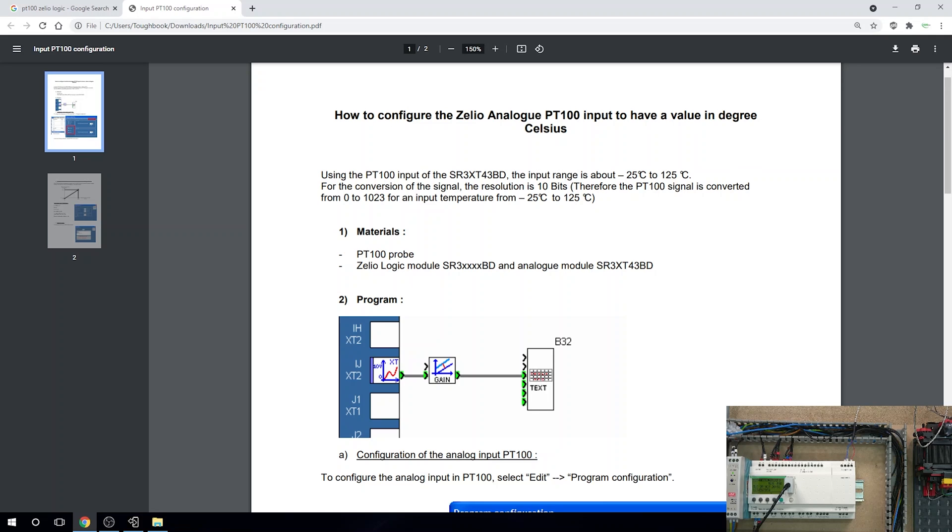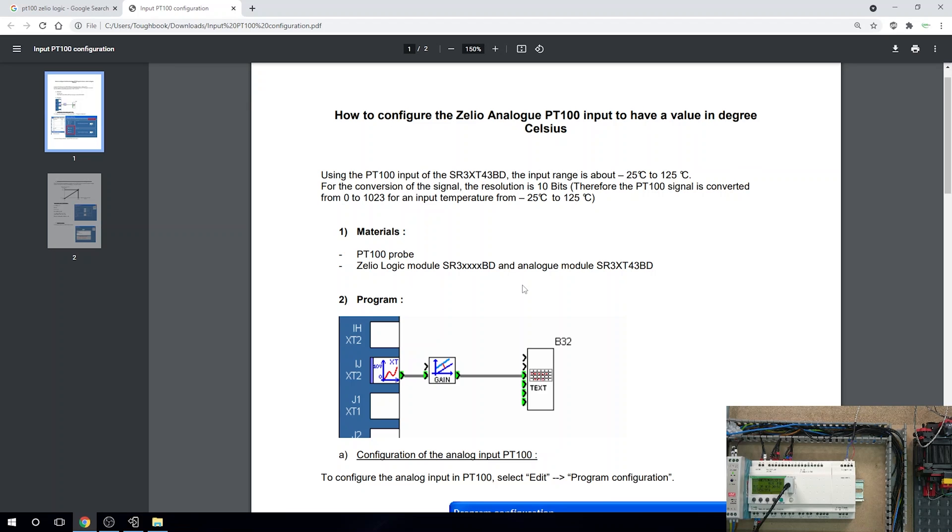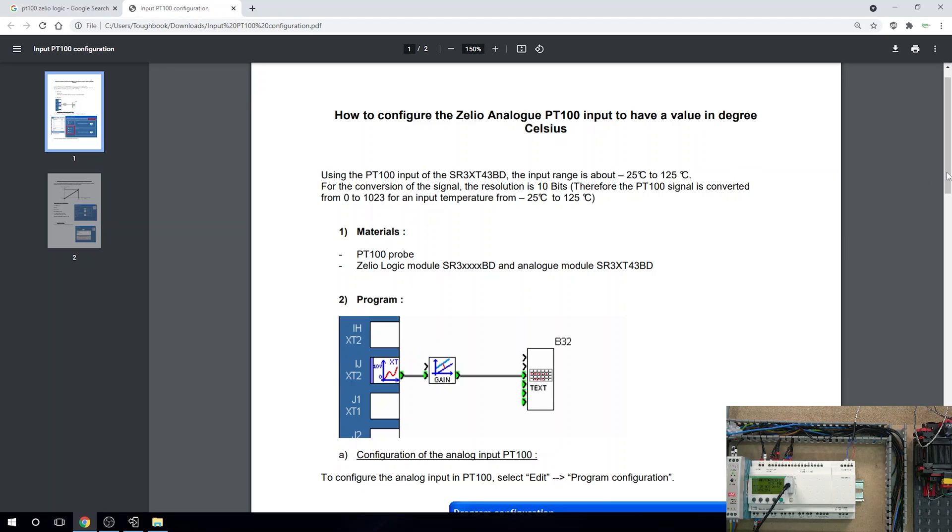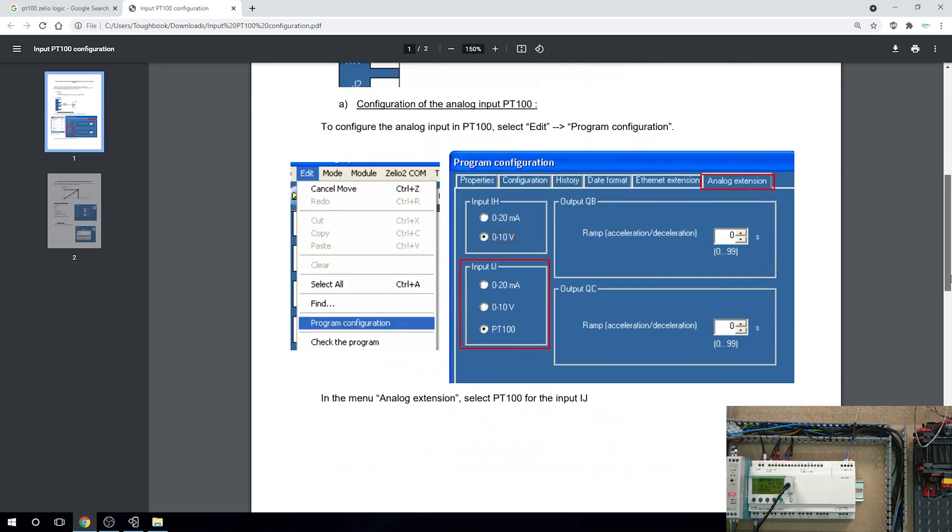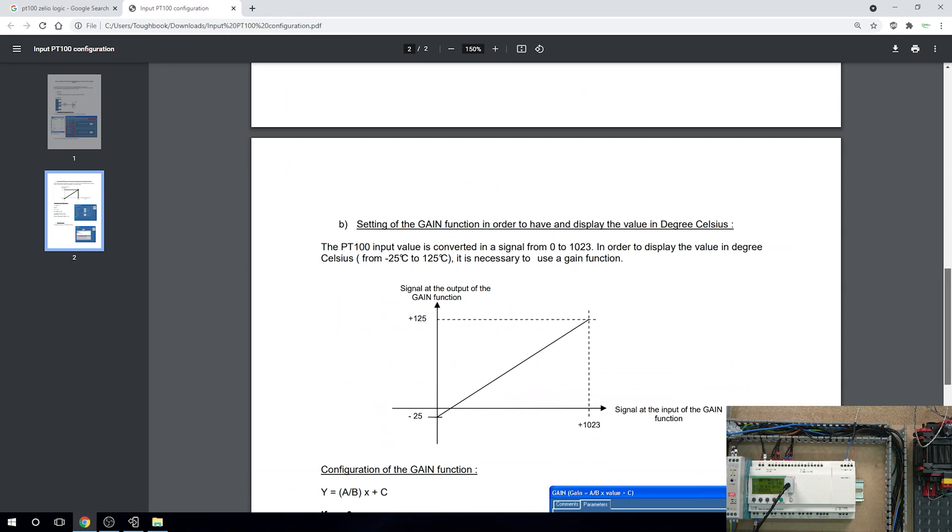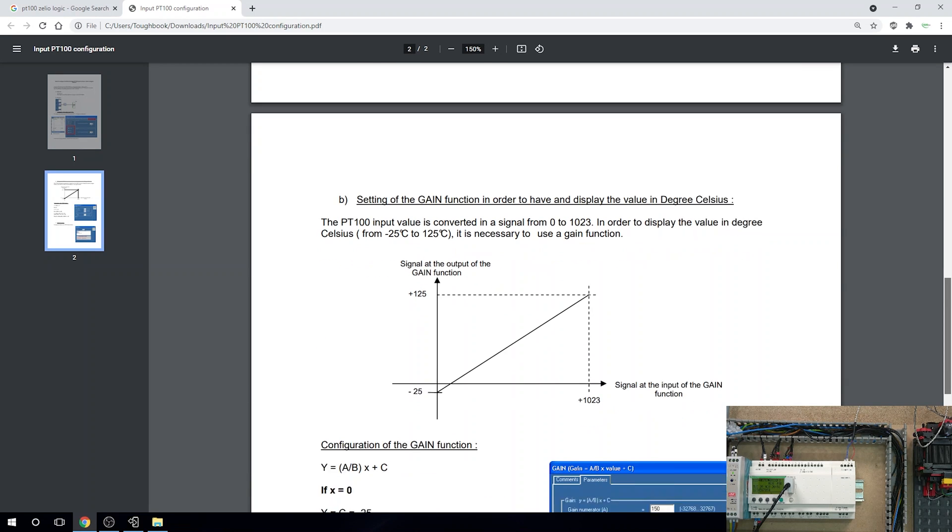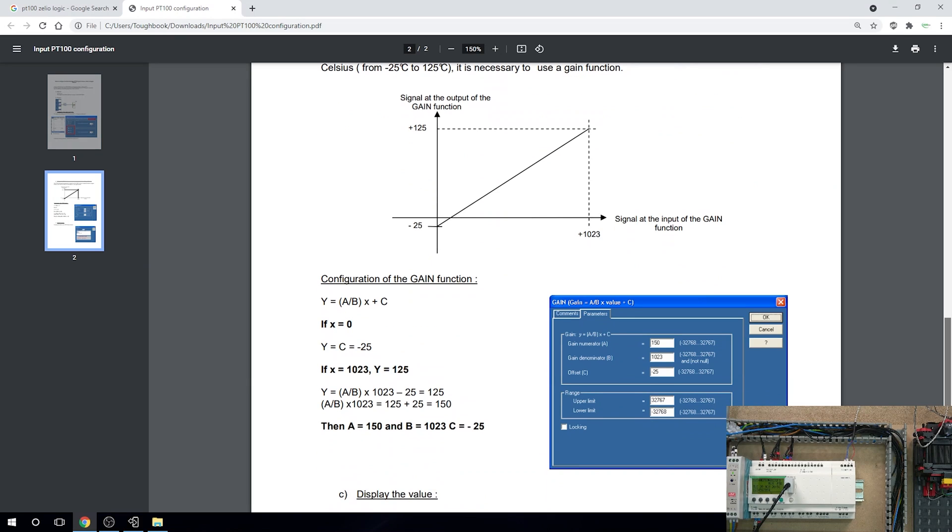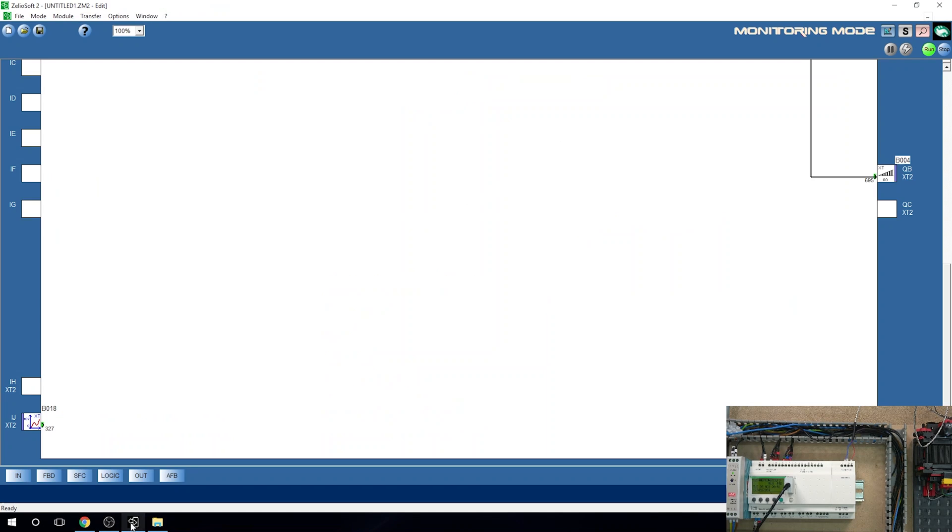Therefore, a PT100 signal is converted from zero to 1023 to represent the temperature range of minus 25 and 125. For us to be able to do that, we will have to use a thing called the gain. It pretty much tells you exactly what values to edit for it to function properly.